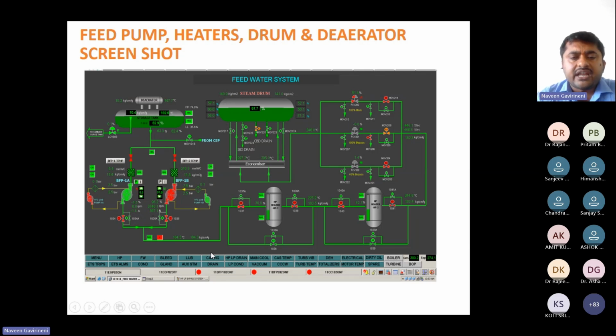In the LP heater, we are getting a 10 to 20 degrees temperature difference, delta T. You just see, this is 184. Here we are getting 225. That means more than 40 degrees temperature rise is there. While coming here, this is 240, 250. So HP heater 1 performs better than HP heater 2. After that, it will go to the economizer. The same temperature, 244. It will increase through the economizer to 295.